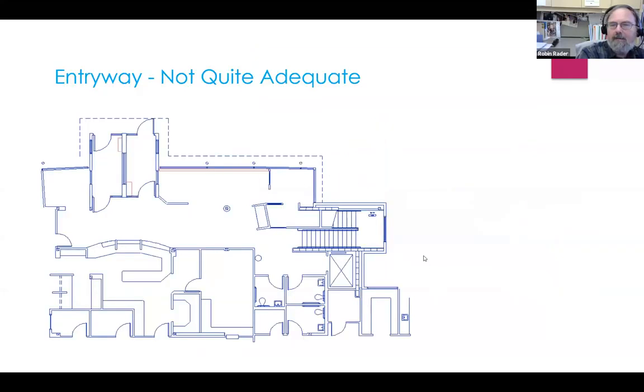So this is a picture of an entry configuration that didn't work. Even though we have split entries and exits, we have a cabinet unit heater on each side of this entry. We didn't put a cabinet unit heater just outside. And so what happens is any cold air that comes out this entry gets pulled along the floor all the way to this piece of fin tube. And so we got seats here for all the occupants, and they are subject to this cold air.